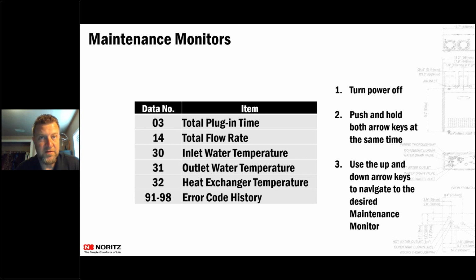So instead of having to tear things down or go through tech support, you could go to maintenance monitor 14 to see what that flow rate is. A lot of times people say, hey, the unit's firing, but we're only getting lukewarm water. We're not getting hot water. So we'll go to maintenance monitor 31 and see what the outgoing water temperature is coming out of the unit. If that water is leaving the unit at 120 degrees, but you're getting lukewarm water at a fixture, then it is something in the plumbing system after the tankless water heater.